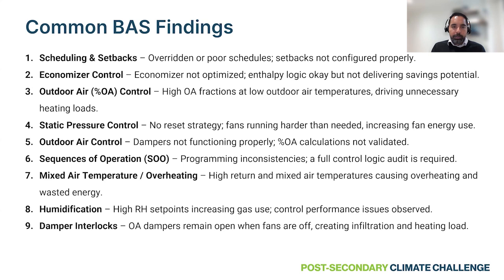Other measures include economizer control, a focus of BAS optimization, where we've seen cases using more cooling energy because the economizer control on air handling systems isn't working. This applies to outside air control too—it's easy to identify how much outside air you're bringing in for each air handling system, unnecessarily increasing your heating load. You can identify these measures through your building's BAS graphics, and we'll show you a few examples.